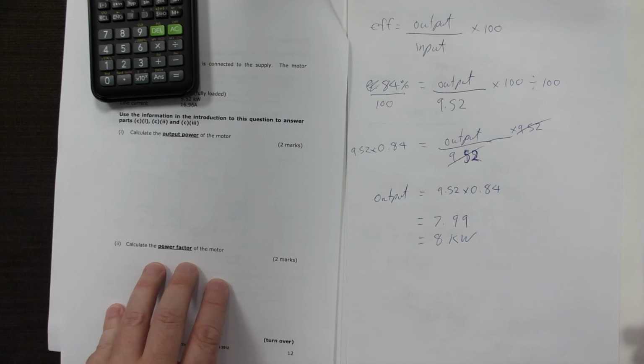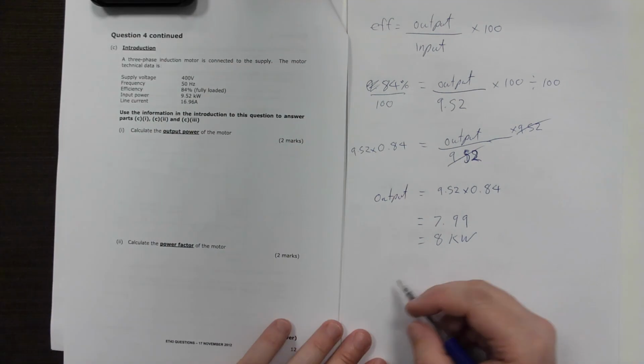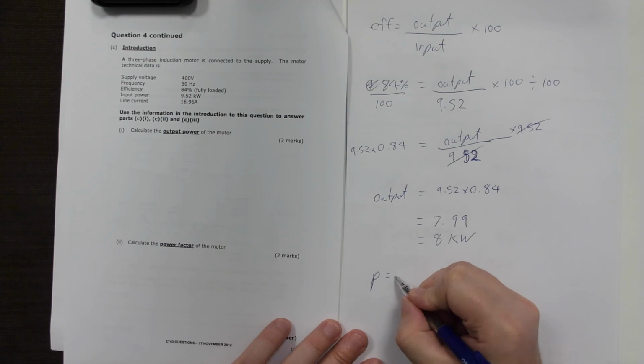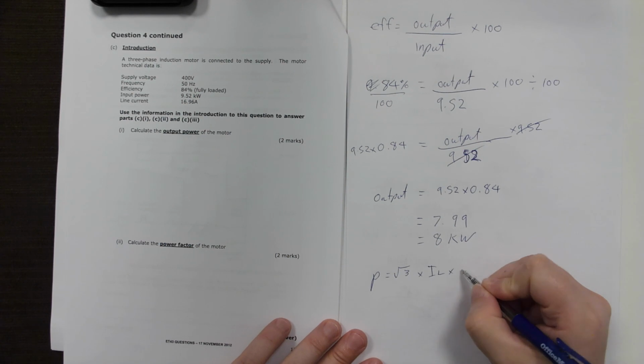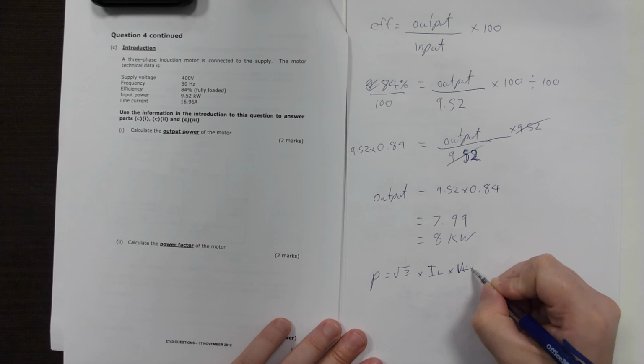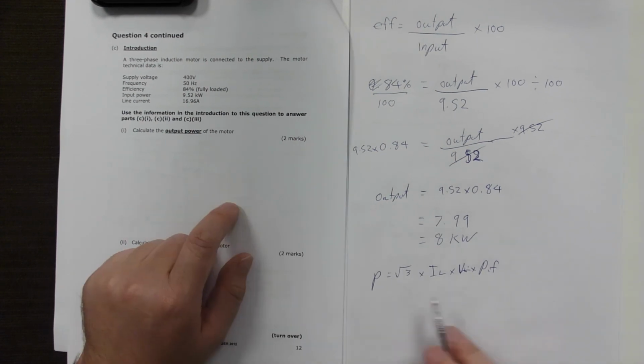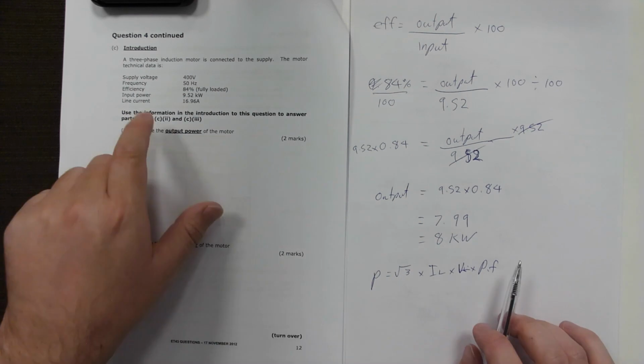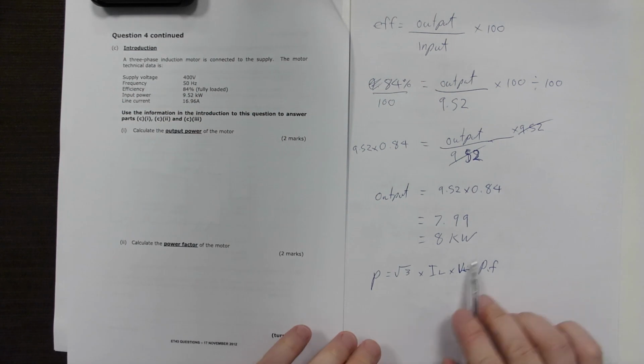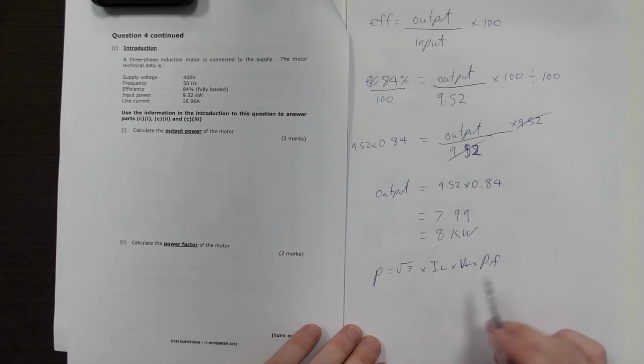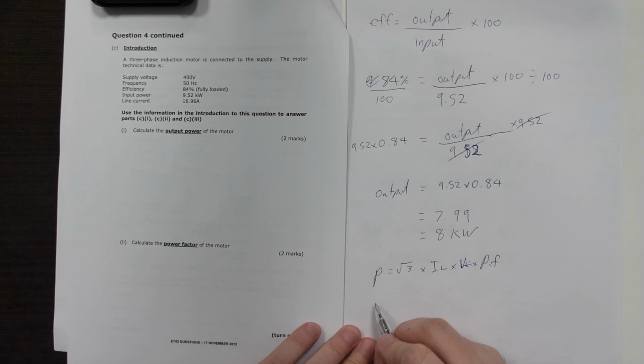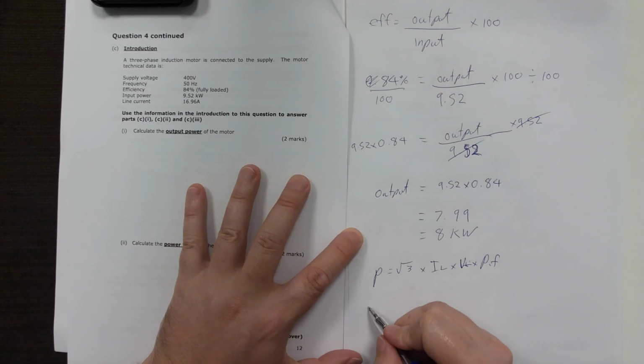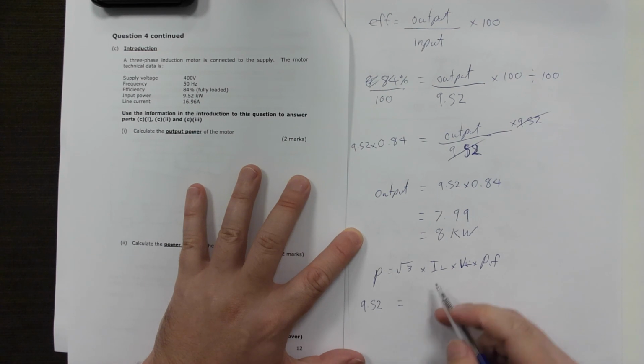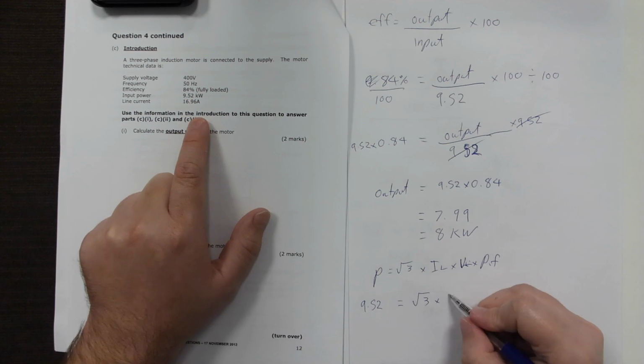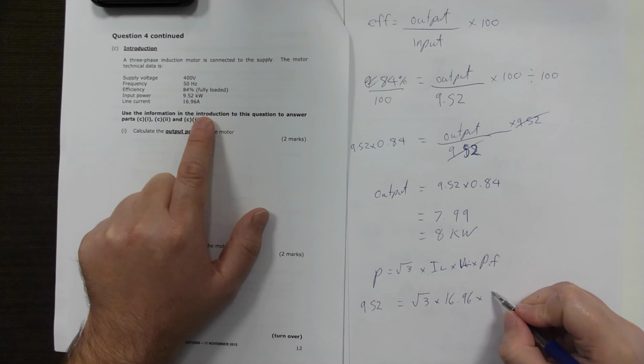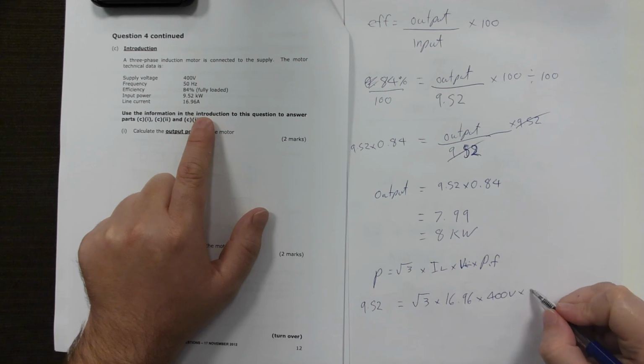Now, on to the next question. Calculate the power factor of the motor. So, our formula for this, power equals root 3 times I line times V line times P.F. Because this is input power, input power multiplied by power factor gives real power, output power. So in this case, we know our input power, which is 9.52, equals root 3 times I line, which is 16.96, times by our V line, which is 400 volts, times by our P.F.